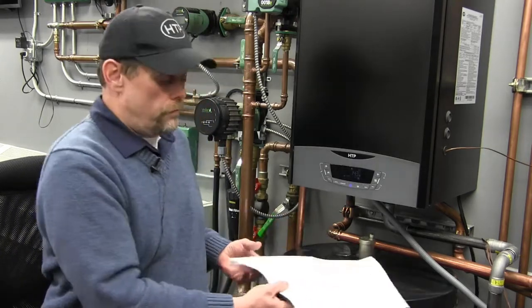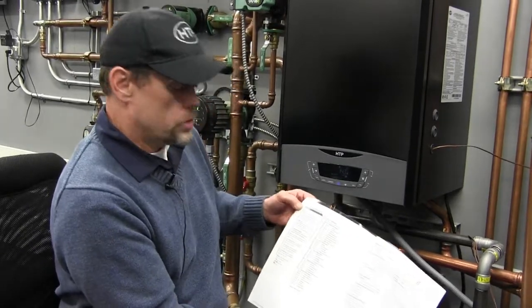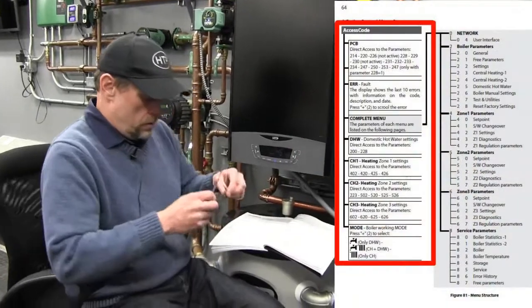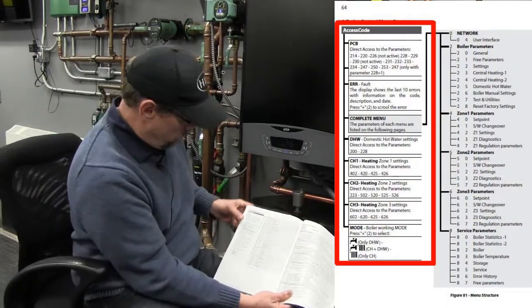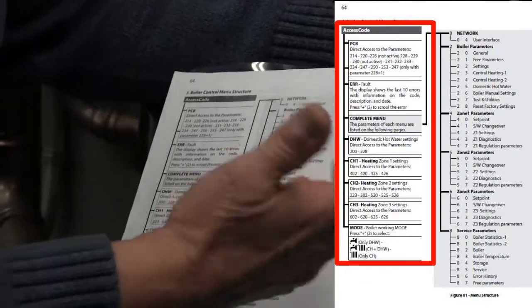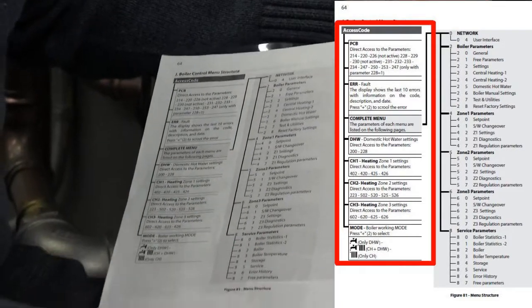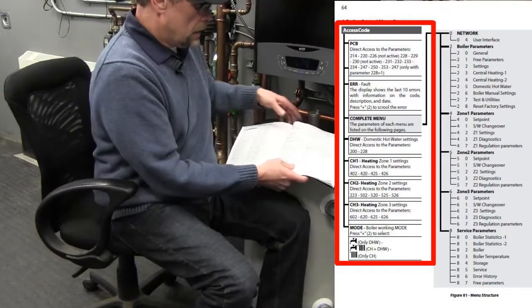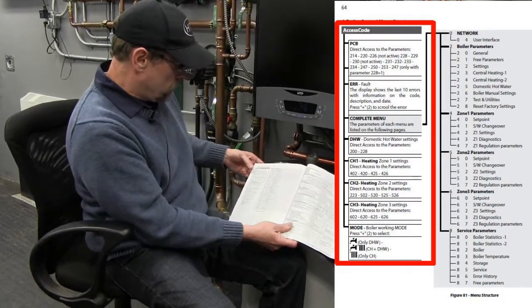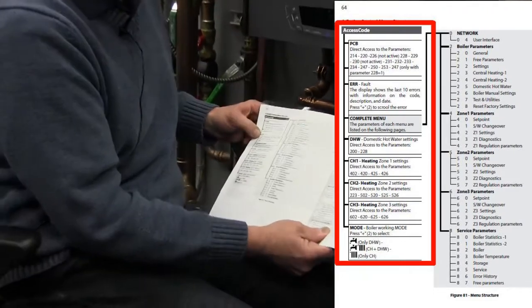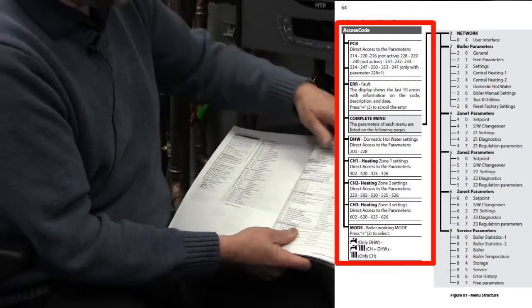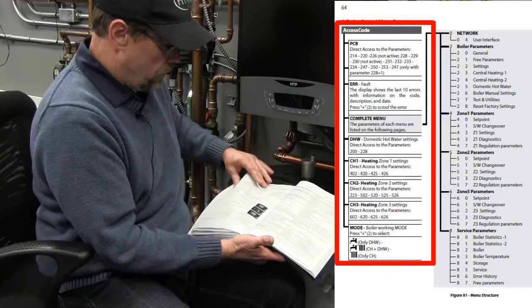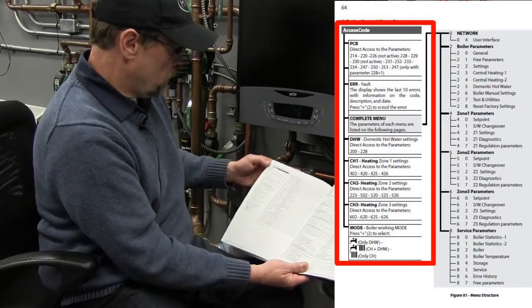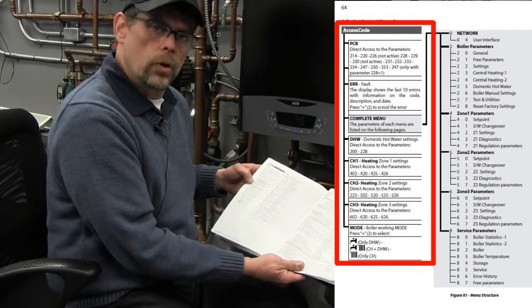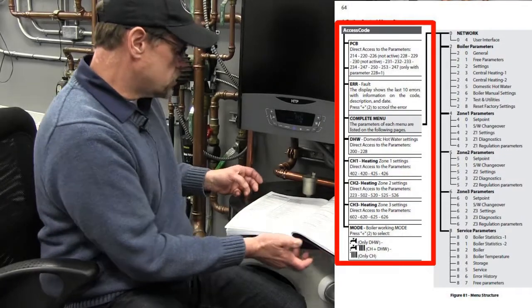So let's do a quick review of where we've been, and what I'm referring to again is the quick access. I'm on page 64. And again, just a quick review. PCB, direct access to the parameters. Those are the boiler parameters. That's just letting the boiler know whether I'm tied to an indirect or whether the indirect has a sensor or an aquastat. Just some of the most basic parameters. We move to the next block, which is the error codes. We just reviewed that. Of course, that's going to come in handy. The complete menu is full access to every single function item in the manual. Next, DHW in the quick access is the most basic functions that the boiler needs to know to start it up. Central 1 heating, that's our zone 1 temperatures.